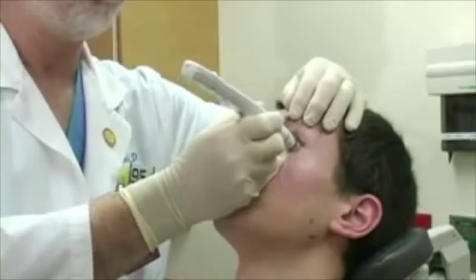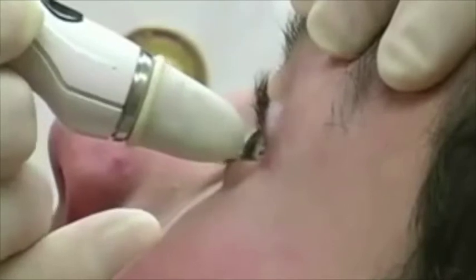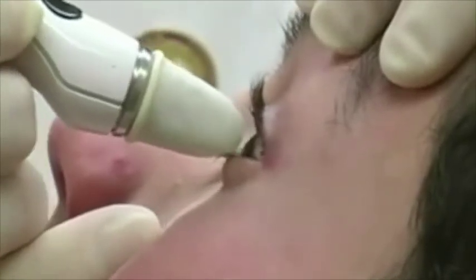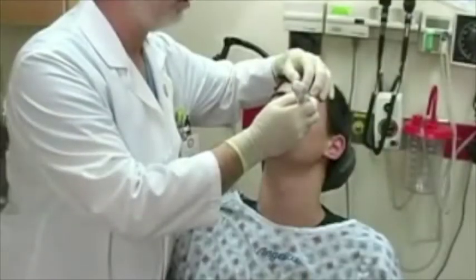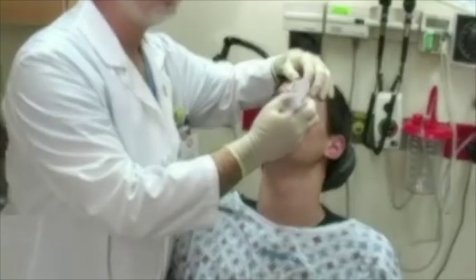Quickly and lightly touch the cornea at least 4 times until 4 valid readings are obtained. A click will sound and a reading will appear on the LCD each time a valid reading is obtained. After 4 valid readings, a final beep will sound and the average measurement will appear on the LCD. The number on the screen represents the intraocular pressure in millimeters of mercury. The bar reflects the statistical reliability of the reading.